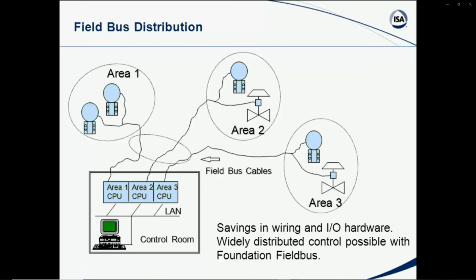Pictorially, this is sort of what we're talking about there, and again there could be some questions here. We're looking at 3 process areas. One of them may be the lime kiln chem, one the recovery boiler, one the paper machine, really whatever. And these have many different types of devices. Transmitters and valves are located all throughout these areas. And these devices are wired to, or hung off of, if you will, the Fieldbus cable, which then is brought inside, and in there is the location. In this particular case, we have not used the control out in the individual smart devices, but we have our processing units located here. That's our controllers.